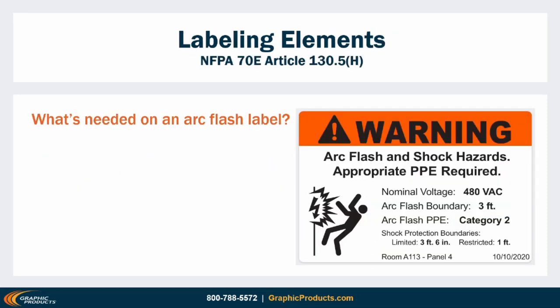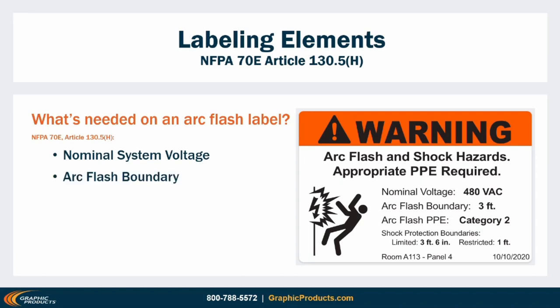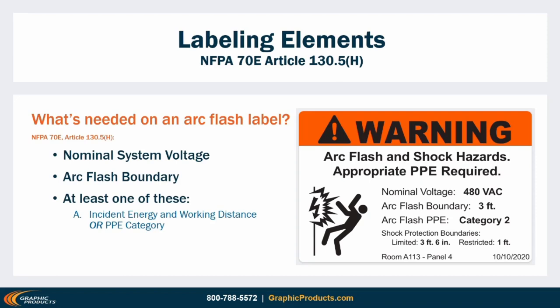Let's say you've collected your information and you're ready to move forward with creating labels. What details actually need to be on the finished label? The label requirements in NFPA 70E are listed in Article 130.5H, and they include: the nominal system voltage, the arc flash boundary, and at least one of the following — the incident energy and working distance, or the arc flash PPE category, but not both — the minimum arc rating of clothing, and/or a site-specific identification of required PPE.